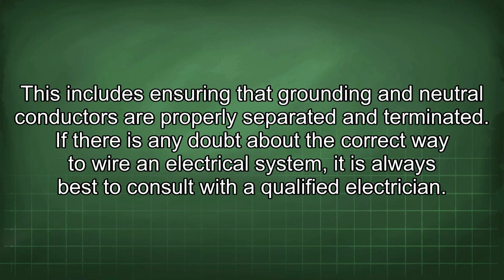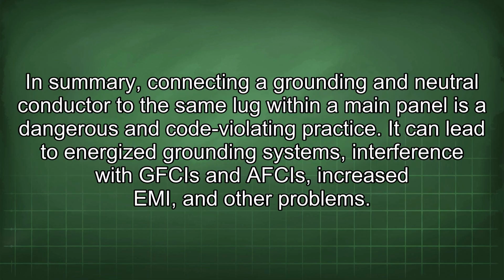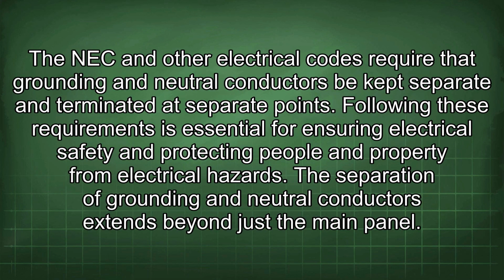If there is any doubt about the correct way to wire an electrical system, it is always best to consult with a qualified electrician. In summary, connecting a grounding and neutral conductor to the same lug within a main panel is a dangerous and code-violating practice. It can lead to energized grounding systems, interference with GFCIs and AFCIs, increased EMI, and other problems. The NEC and other electrical codes require that grounding and neutral conductors be kept separate and terminated at separate points. Following these requirements is essential for ensuring electrical safety and protecting people and property from electrical hazards.